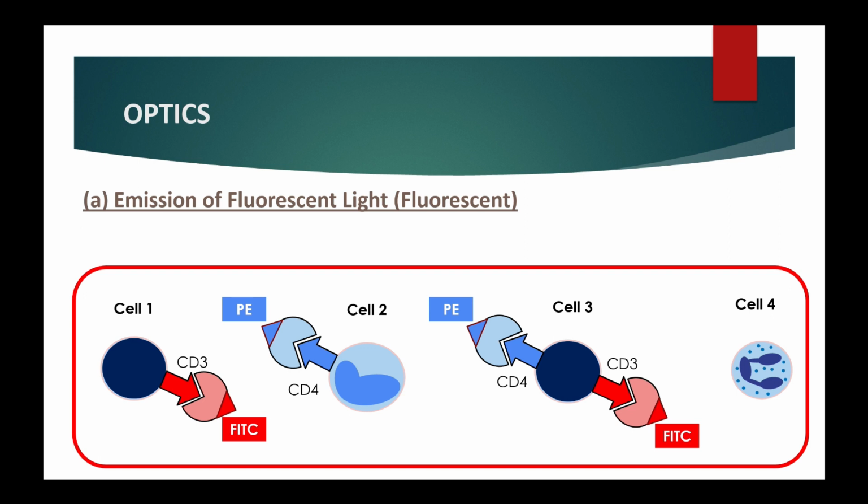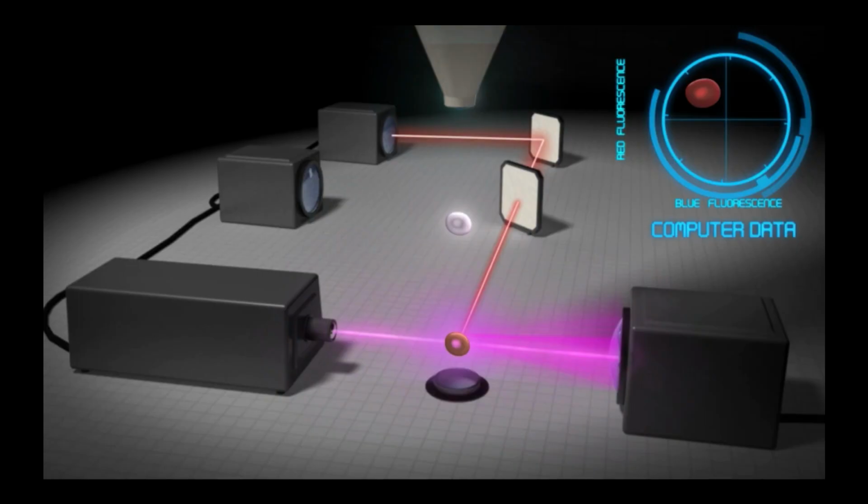The cells are labeled with fluorochrome linked antibodies. As the fluorescent molecule present in or on the cell is interrogated by a laser light, it will absorb energy from the laser and release the absorbed energy at longer wavelength. Emitted photons pass through the collection lens and are split and steered down specific channels with the use of filters.